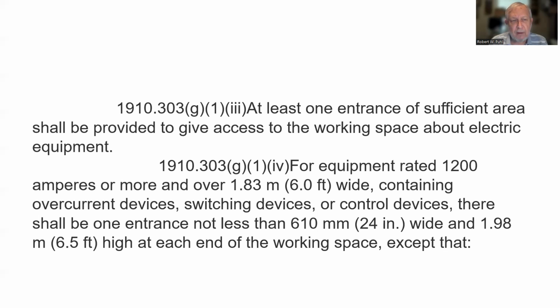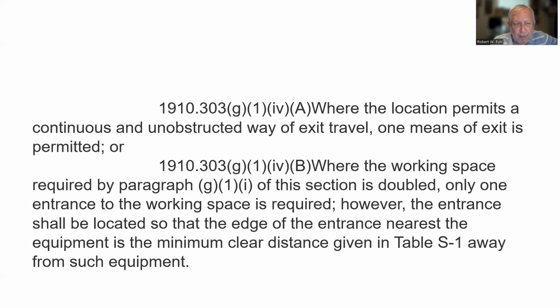At least one entrance of sufficient area shall be provided to give access to the working space about electric equipment. For equipment rated 1200 amperes or more and over 6 feet wide, containing overcurrent devices, switching devices, or control devices, there shall be one entrance not less than 24 inches wide and 6.5 feet high at each end of the working space, except that where the location permits a continuous unobstructed way of exit travel, one means of exit is permitted, or where the working space required by paragraph G1I of this section is doubled, only one entrance to the working space is required. However, the entrance shall be located so that the edge of the entrance nearest the equipment is the minimum clear distance given in table S1 away from such equipment.